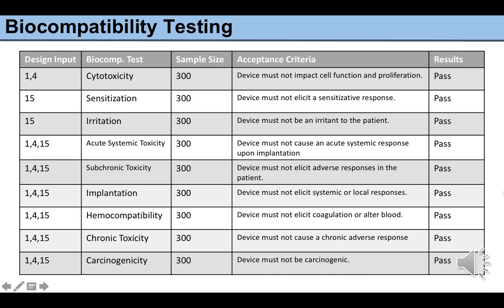Completed biocompatibility testing. For this, we followed ISO 10993-1 and FDA testing requirements. For cytotoxicity, we looked at the device components tested in mammalian cell culture, monitoring proliferation and death in an incubator at 37 degrees Celsius. For sensitization, we used guinea pig maximization testing to follow whether or not the sensitivities would appear once the device is implanted.